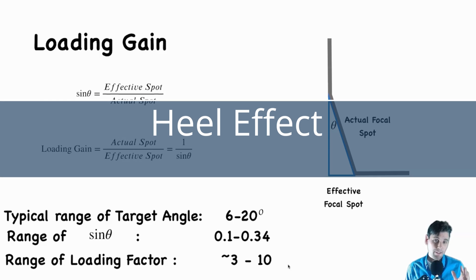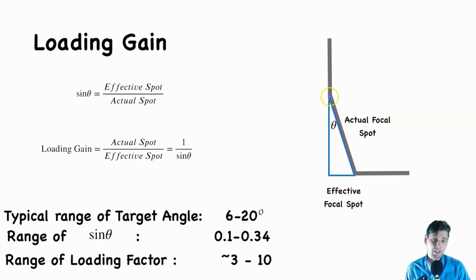One downside of having very shallow angles is something called the heel effect, or the anode heel effect. It gets worse at smaller angles because the x-rays coming out of this region are traveling through more of the material compared to x-rays coming out through the other region. We have a separate video talking about that heel effect.